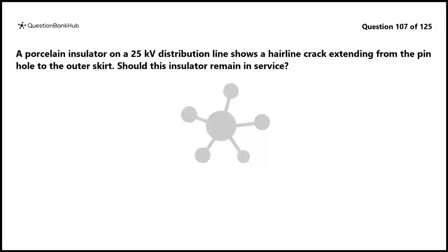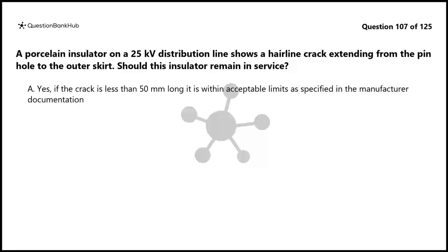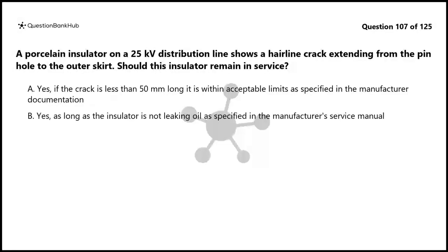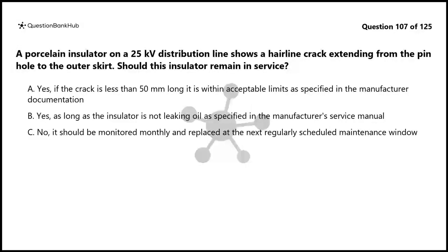Question 107. A porcelain insulator on a 25 kV distribution line shows a hairline crack extending from the pinhole to the outer skirt. Should this insulator remain in service? A. Yes, if the crack is less than 50 mm long, it is within acceptable limits as specified in the manufacturer documentation. B. Yes, as long as the insulator is not leaking oil as specified in the manufacturer's service manual. C. No, it should be monitored monthly and replaced at the next regularly scheduled maintenance window. D. No, any crack that extends from the pinhole to the outer skirt compromises the insulating path and requires immediate replacement.